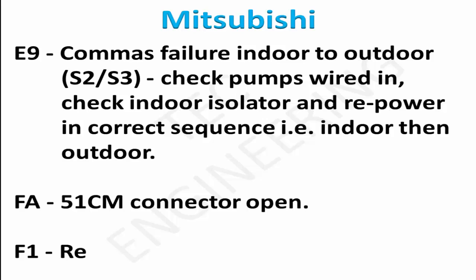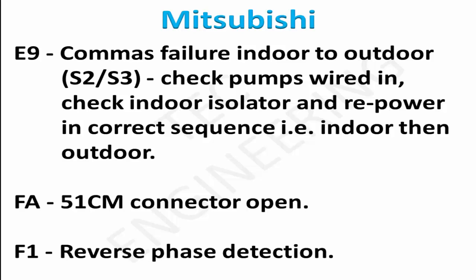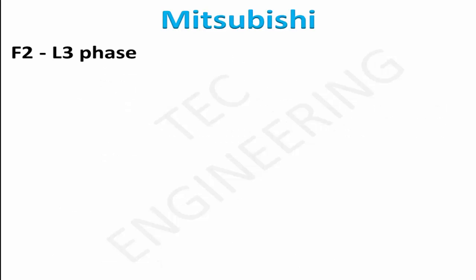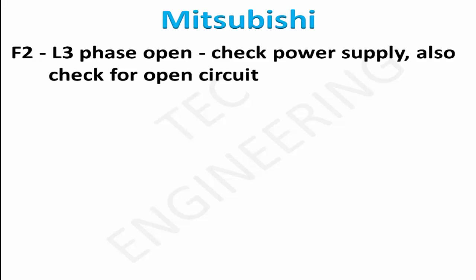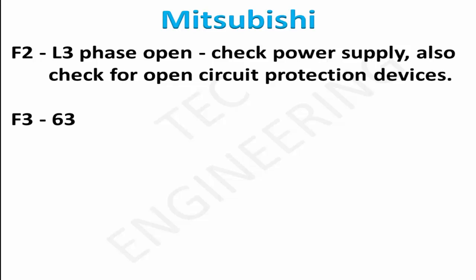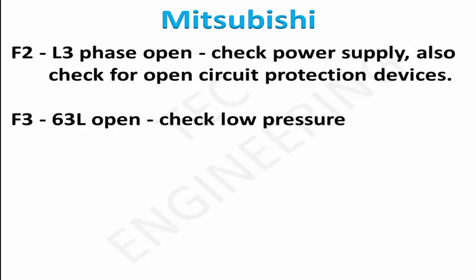F1: reverse phase detection. F2: L3 phase open — check power supply, also check for open circuit protection devices. F3: 63L open — check low pressure switch for disconnection or contact failure.